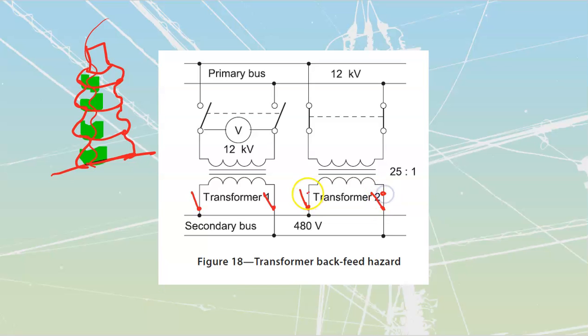Okay? Not always needed, but if you're paralleling, it's very good form to have a second one on there, because now I would be able to keep this one closed. I should close that one, like that. I would be able to open this one. When I open this one, that transformer backfeed hazard doesn't exist because the electricity can't get through to here to flux the core and flux this side. Therefore, this would no longer be at 12 kV. This would be 0 volts that I would have off of it.